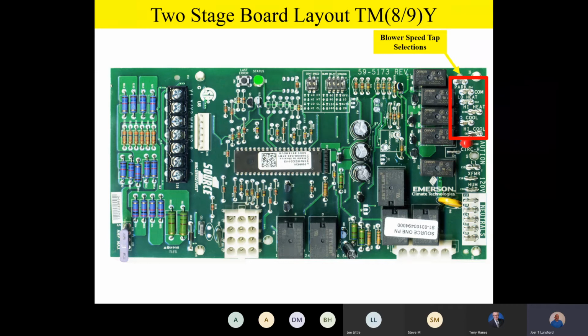Right below that, we have a 120 volt EAC terminal for an electronic air cleaner. Now remember, team, that it is 120 volts, so be careful. Below that, we have a circ terminal. That circ terminal is that wire that powers up the ECM indoor blower all the time. Remember, team, the ECM blower is powered all the time. That's where we grab power. We call it circ on this board.